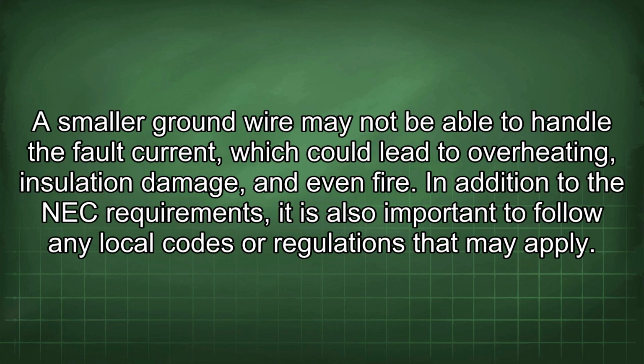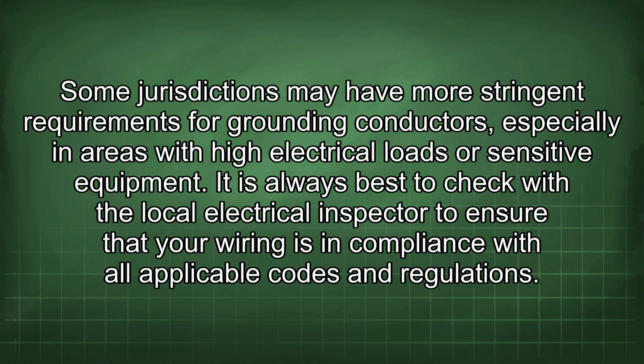A smaller ground wire may not be able to handle the fault current, which could lead to overheating, insulation damage, and even fire. In addition to the NEC requirements, it is also important to follow any local codes or regulations that may apply. Some jurisdictions may have more stringent requirements for grounding conductors, especially in areas with high electrical loads or sensitive equipment. It is always best to check with the local electrical inspector to ensure that your wiring is in compliance with all applicable codes and regulations.